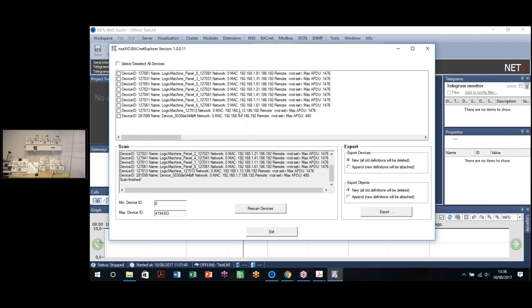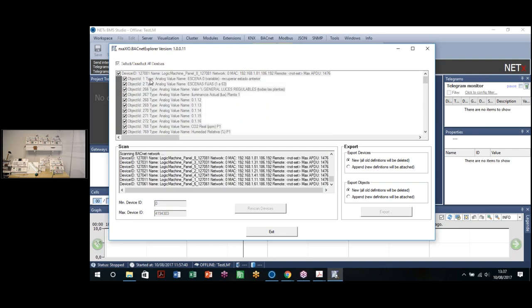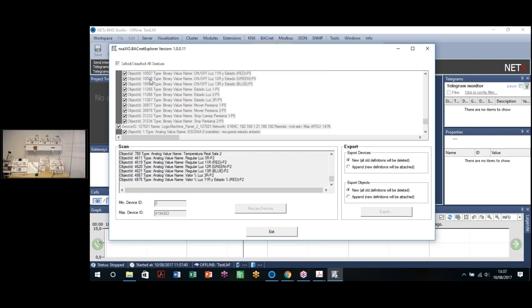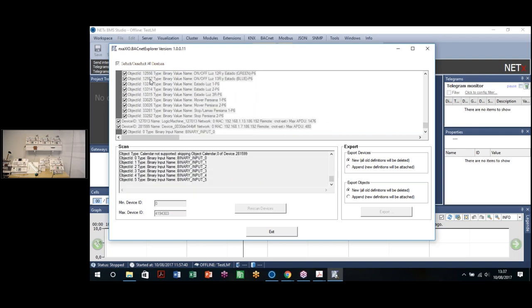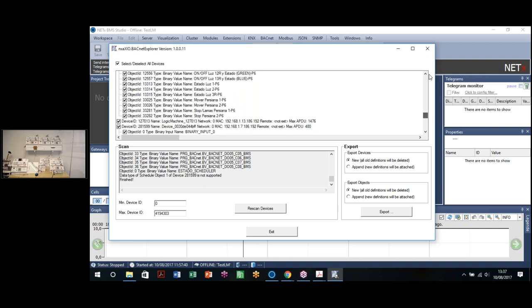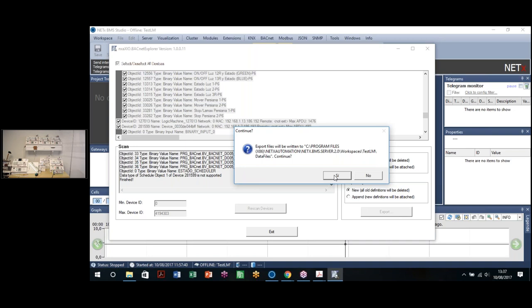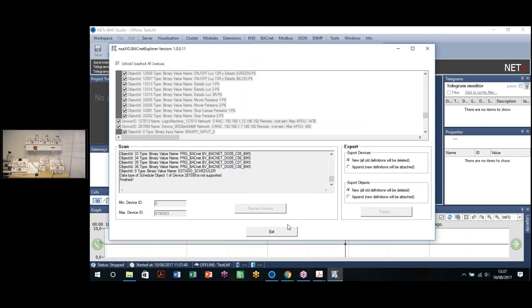So we have IPs 13, 11, 21, 31, 41. So all these devices are LogicMachine, as you can see here. And also we have another one. Just select wherever you want. I select everything, and it's automatically read by the BMS, and when it finishes reading objects for all of them, which takes some time, we can export all these objects in a unique item tree. So we can have all these LogicMachine objects together. You can see we have a lot. Then just select export, say yes, we want to create new files. Once everything is okay, we can exit and see the BACnet objects successfully exported.